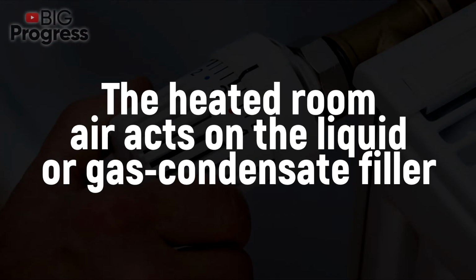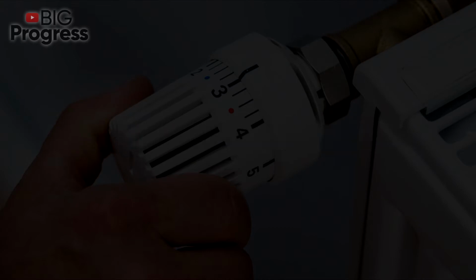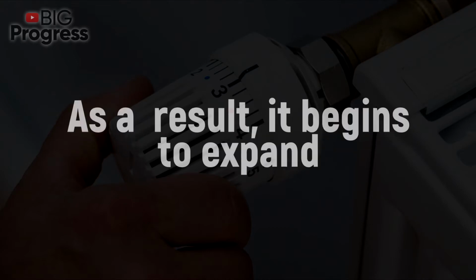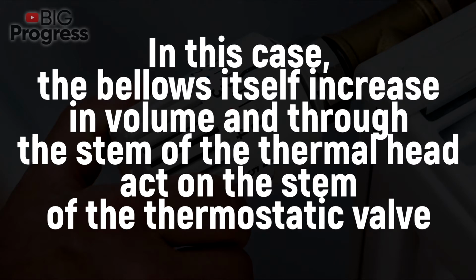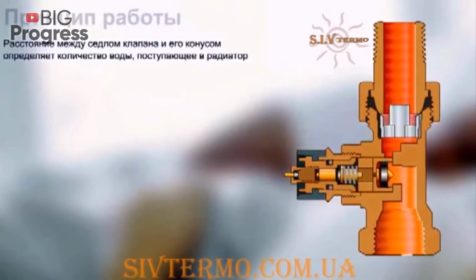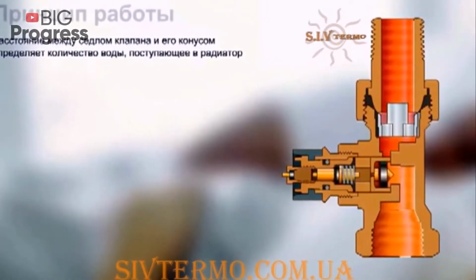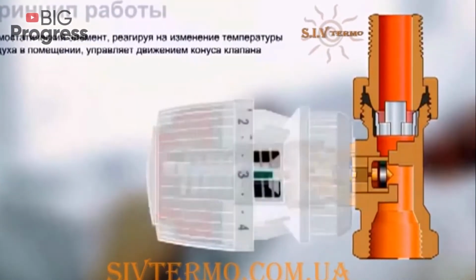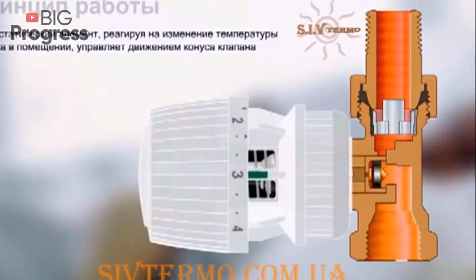The air in the heated room acts on the liquid or gas condensate filler, which is in a closed space. As a result, it begins to expand. In this case, the bellows itself increase in volume, and through the stem of the thermal head act on the stem of the thermostatic valve. The valve in turn, by means of a special cone that moves downward, reduces the passage and thereby limits the amount of coolant entering the radiator.